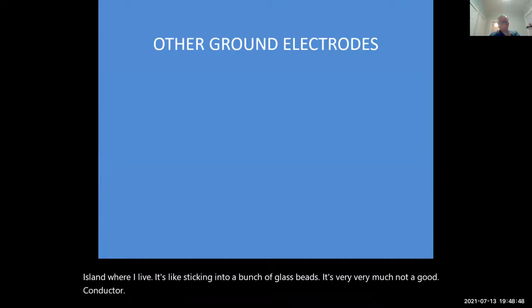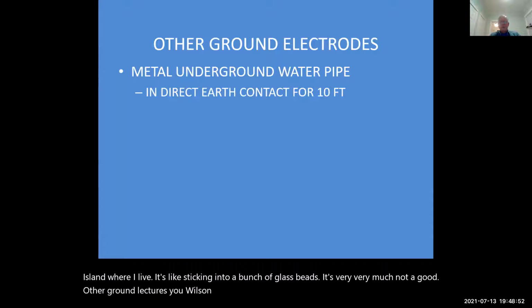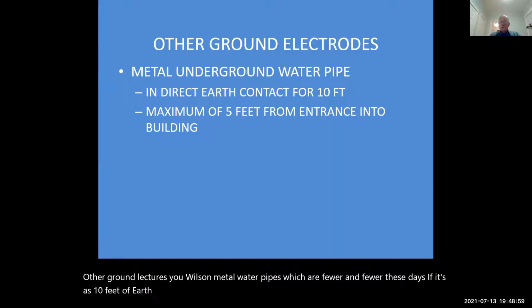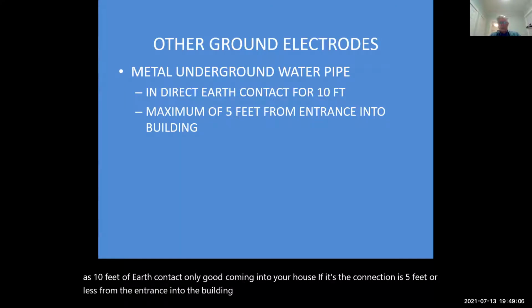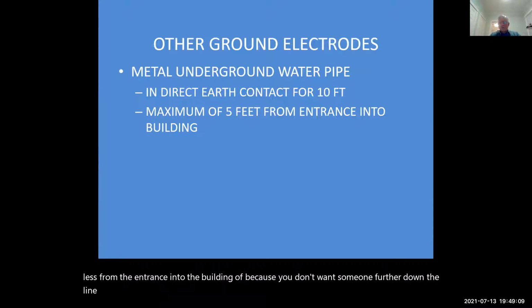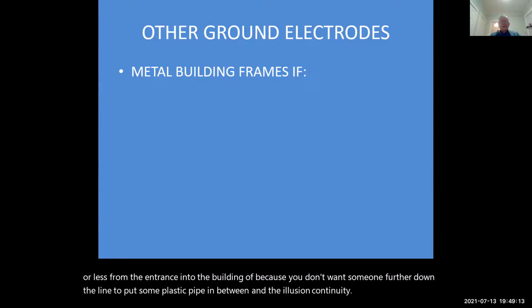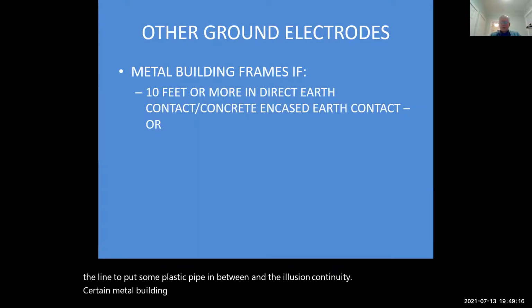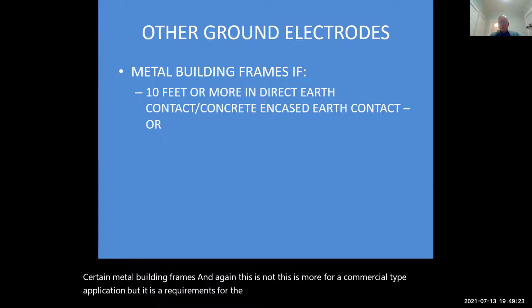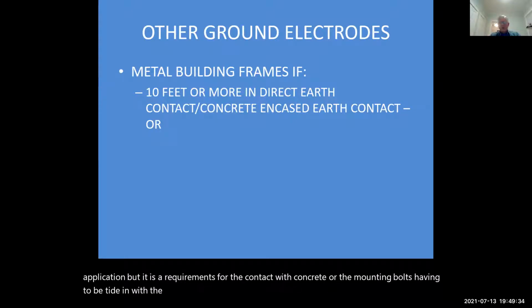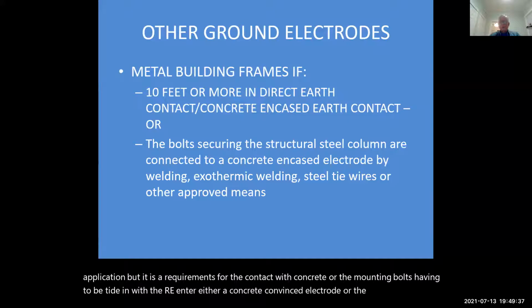Other ground electrodes, you will see metal water pipes, which are fewer and fewer these days. If it has 10 feet of earth contact, it's only good coming into your house if the connection is 5 feet or less from the entrance into the building, because you don't want someone further down the line to put some plastic pipe in between and you lose your continuity. Certain metal building frames, and again, this is more for a commercial type application, but there are requirements for the contact with concrete or the mounting bolts having to be tied in with either a concrete based electrode or steel in the concrete.